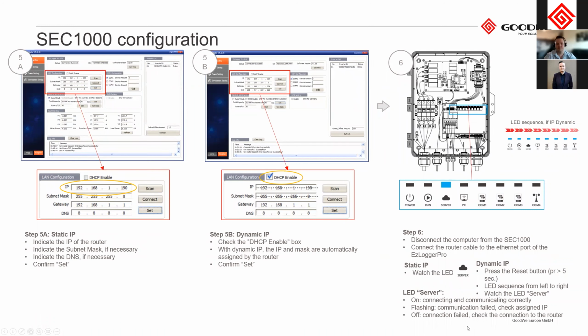So once we've confirmed our inverter is working well, we now have to connect the SEC to the network. This is normally the last step we're going to do, because once we do this, we've connected it to the customer's network. So there's two ways of doing this. Ideally, static mode will always be the best to use, but it is slightly more complicated. Normally, if it is a commercial site and you are connecting to the customer's network, you'll have to find from their IT team an IP address range or IP address that you can use, as well as the gateway. All of this information you'll have to get from the IT team, that you can then insert here and set that to a static IP address.